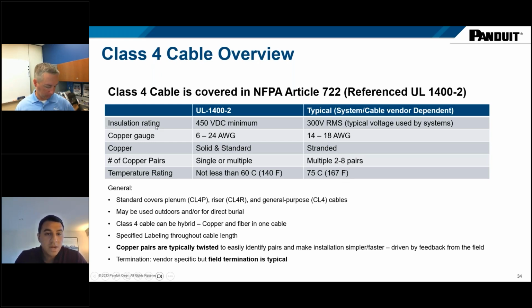In terms of insulation rating, your cable has to be able to handle 450 volts at a minimum, but you'll typically see systems out there operating in the 300 volt RMS range. In terms of copper gauge, the standard covers anywhere from 6 to 24 gauge. Again, typically you'll see 14 to 18 gauge cable. It covers solid and stranded, though you'll typically see stranded. It covers the number of copper pairs, single or multiple, and typically these cables come in multiples of 2, anywhere from 2 to 8 pairs.